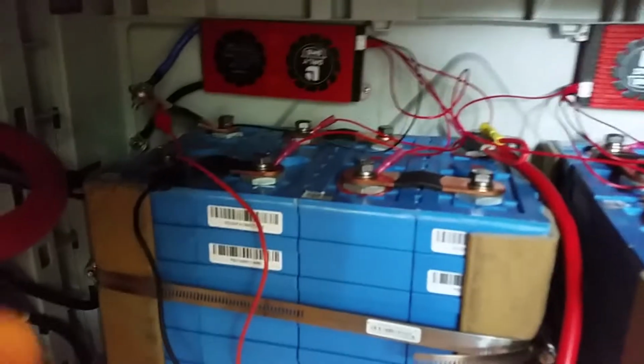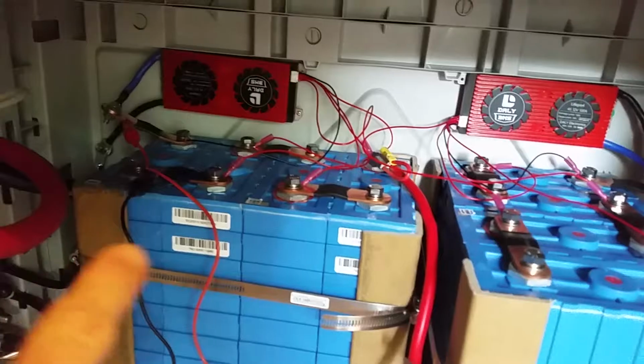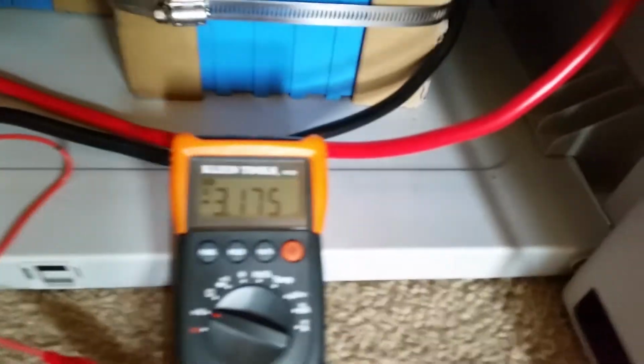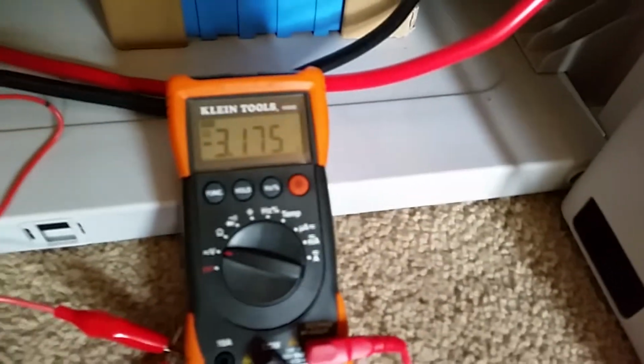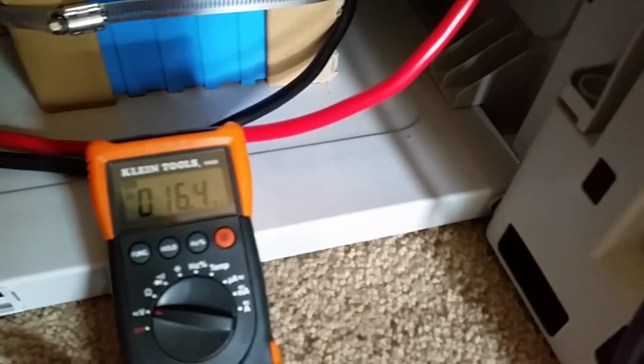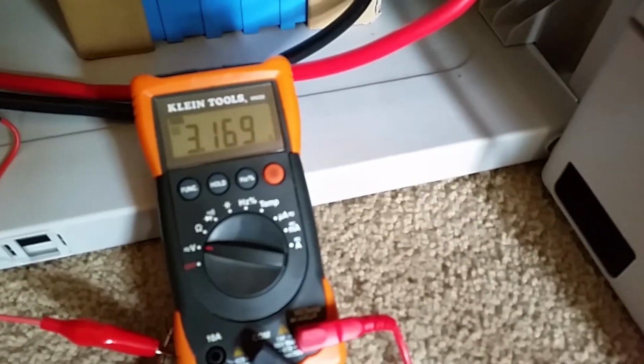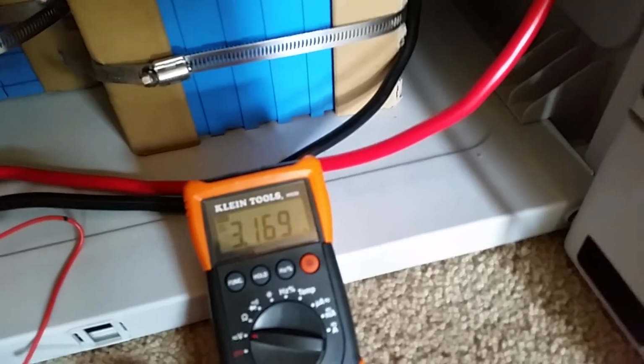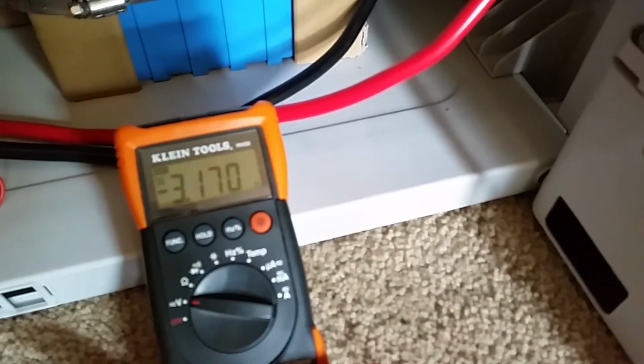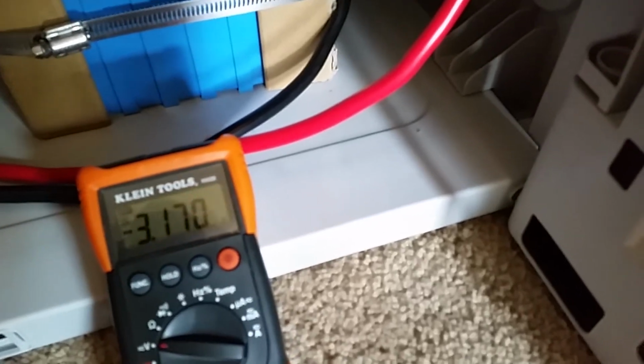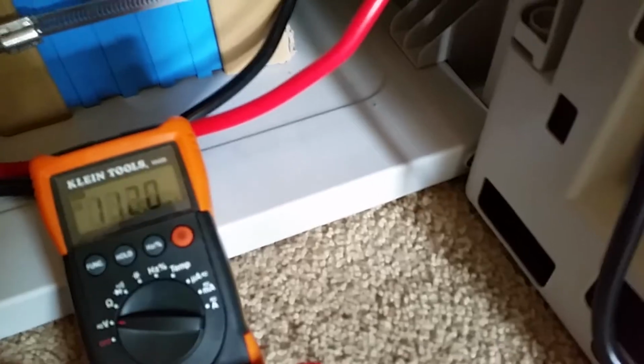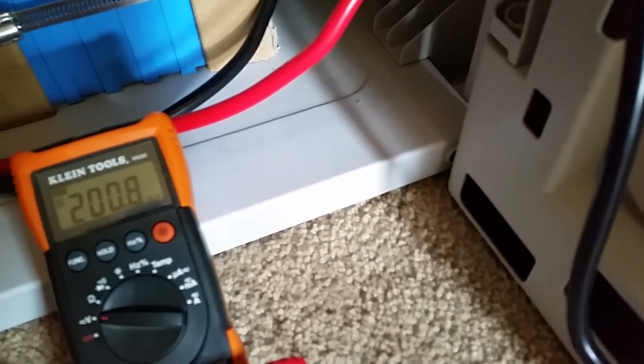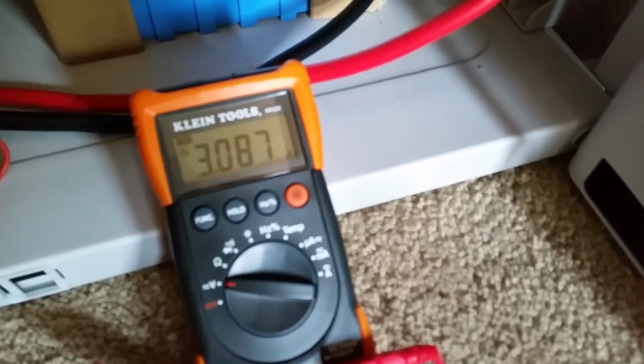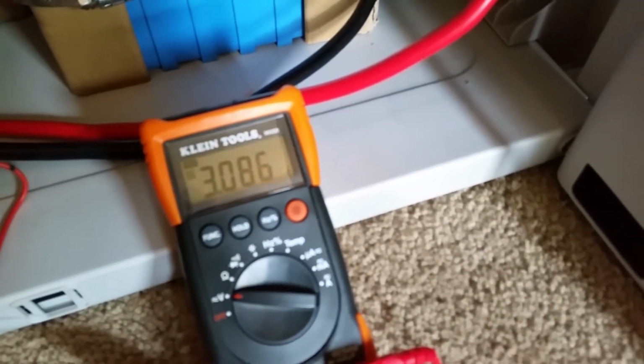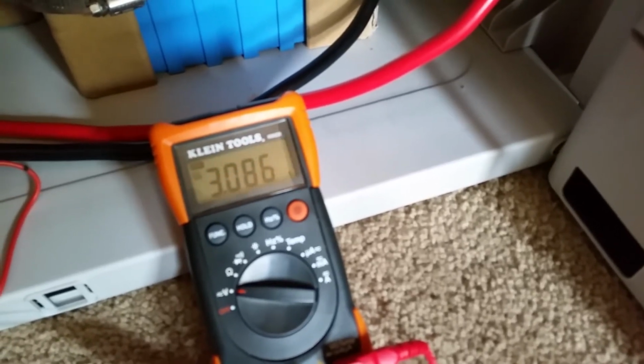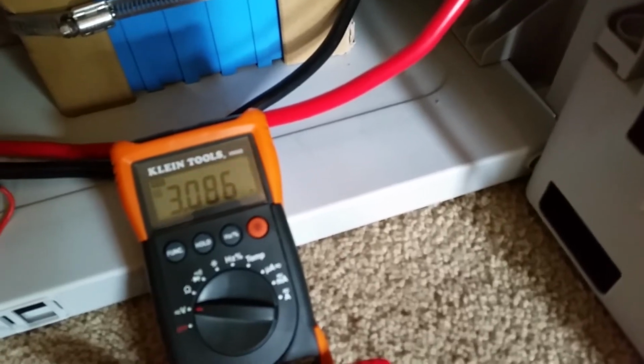This first cell over here, on the far left of this 12 volt bank, is reading 3.175. The next one over is 3.169, about the same, 3.170. The next one over is 3.087, so that's a little bit off, not too bad—less than 0.1 volts off for load testing.